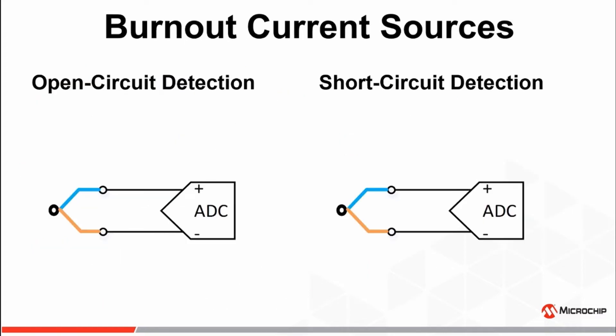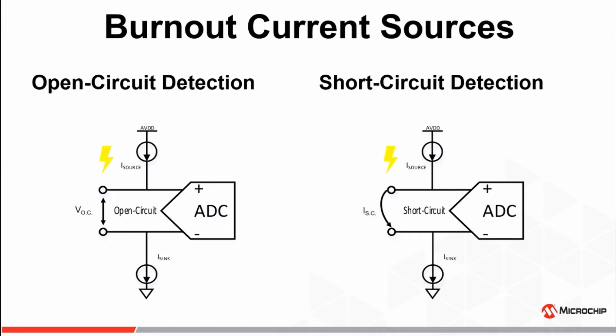Here we illustrate the use of the burnout current sources for fault detection in sensors such as a remotely connected thermocouple. Since thermocouples are sensors which require no external excitation voltage, such as you would see with a strain gauge, detection of open and/or short circuit conditions is fairly simple, as all it requires is the activation of the burnout current sources on the VIN-plus and VIN-minus inputs. In the case of an open circuit, when enabled, the I-source DAC will pull the VIN-plus input to AVDD and the I-sink DAC will pull the VIN-minus input down to ground.